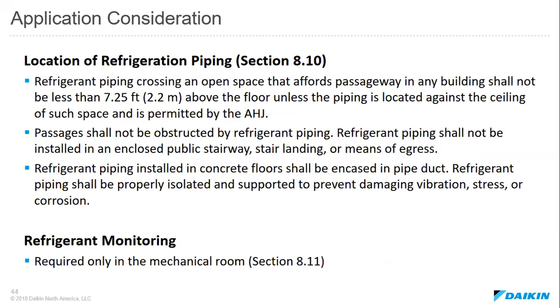So, application considerations, something to think about, are the refrigerant piping. One of the things to keep in mind when laying out a VRF project is that refrigerant piping crossing an open space of a passageway must be at least 7.25 feet above the floor, unless the piping is located against the ceiling of such space. This is all based on the local jurisdiction codes. Passages can't be obstructed by refrigerant piping, so the refrigerant piping can't be installed in enclosed stairwells or other areas of egress. And finally, refrigerant piping installed in concrete floors should be encased in a concealed pipe or duct.